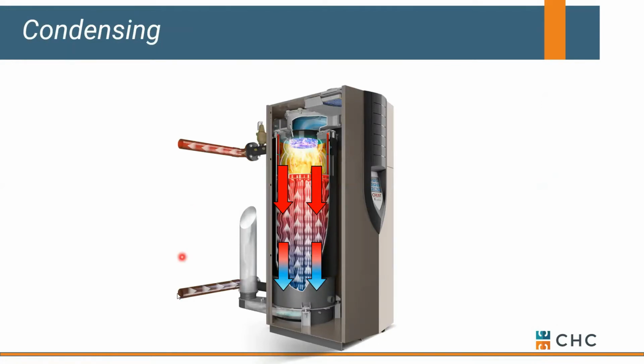If you bring cold water back to a boiler, meaning less than 130 degrees, you're actually going to cool down the products of combustion, in this case your natural gas, below its dew point, and as a result you're going to get some moisture that comes out. Okay, and that moisture, again, is on the flue product side, or your gas side. It's going to collect down here into a collection pan and then get out of the boiler.